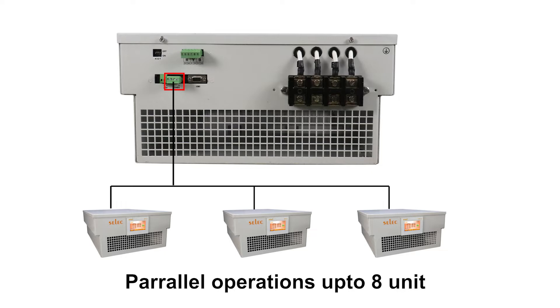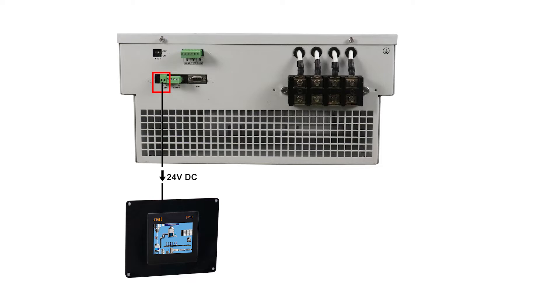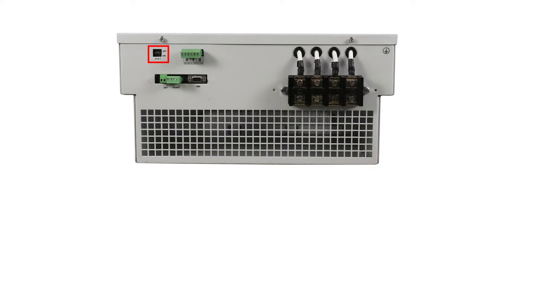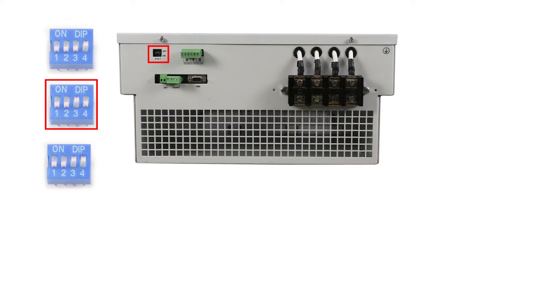Communication amongst modules happens through this RS485 connector. 24 volt is for the HMI — the HMI requires 24 volt which is connected from here. This is the DIP switch setting for setting the slave ID of this module. Suppose there are 3 such modules connected: you will set the first module in binary as 0001, the second as 0010, and the third as 0011.